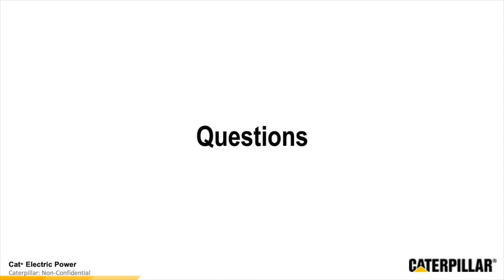So that's where it's a little bit confusing, but typically an 80% rated breaker is going to be a little bit less expensive than a 100% rated breaker. But if you have an application where you know you're not going to be running at the full rating, that it's going to be something less the majority of the time, then you might want to put an 80% rated breaker in because it'll be less cost for you overall.